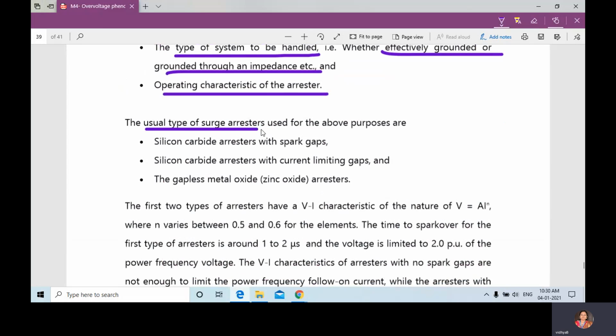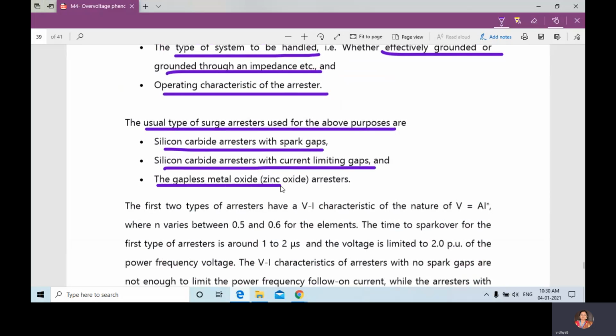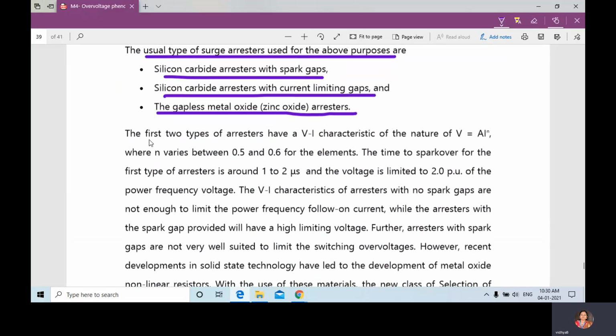The usual types of surge arrestor used for the above purpose are, first, silicon carbide arrestor with spark gap, silicon carbide arrestor with current limiting gap, and gapless metal oxide, that is, zinc oxide arrestors. The first two types of arrestor have a VI characteristic of the nature V is equal to A into I to the power of N. N varies from 0.5 to 0.6 for the elements.